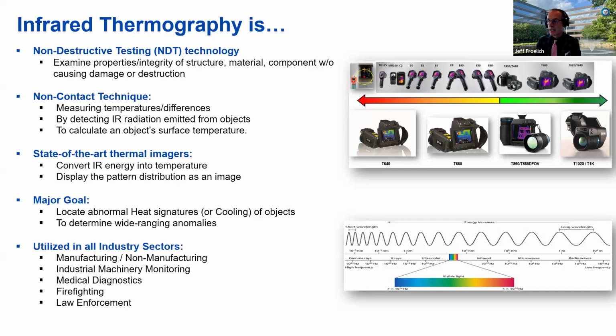It's done live and energized, and you must have line of sight. So don't be fooled that if you have an infrared inspection done, yep, we're all good to go, a survey was done. You might have a lot of equipment that couldn't be opened due to arc flash, something we'll talk about here in a few minutes, or due to an interlocked machine, or due to conditions beyond control.